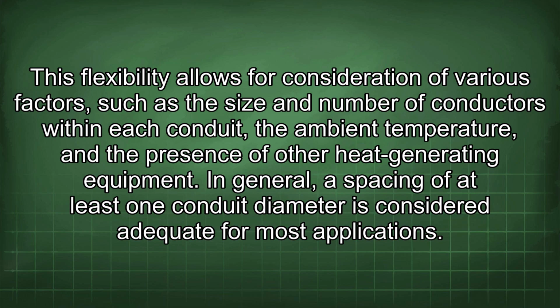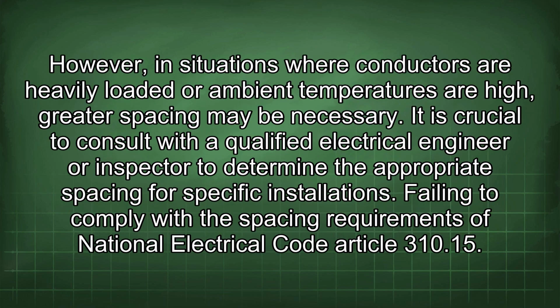In general, a spacing of at least one conduit diameter is considered adequate for most applications. However, in situations where conductors are heavily loaded or ambient temperatures are high, greater spacing may be necessary. It is crucial to consult with a qualified electrical engineer or inspector to determine the appropriate spacing for specific installations.